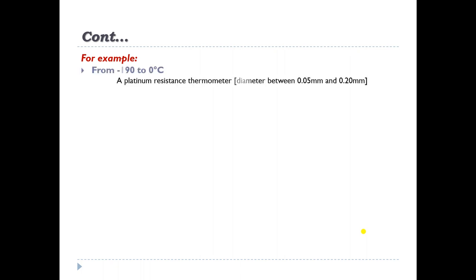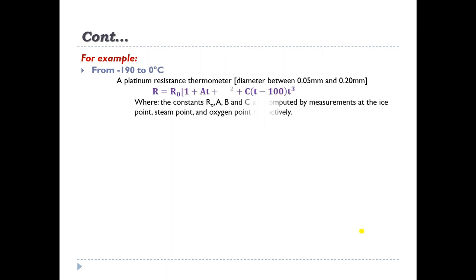From −190°C to 0°C, a platinum resistance thermometer with platinum wire of diameter between 0.05 mm and 0.20 mm is used. The temperature is defined by a polynomial of the form R = R₀(1 + AT + BT² + C(T − 100)T³), where the constants R₀, A, B, and C are computed from measurements at the ice point, steam point, and oxygen point respectively.